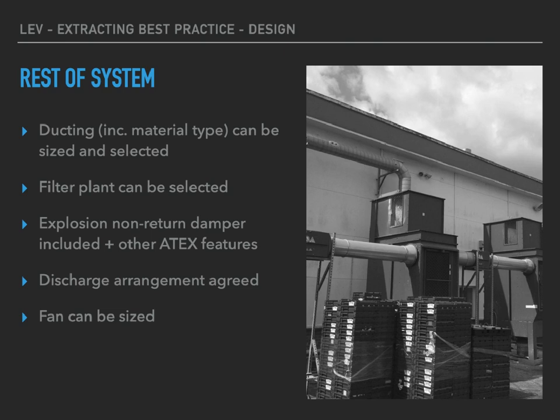We have to consider the rest of the system as well. There are many, many features that need to be considered by the designer of the LEV system. Some critical factors include the number and size of the hoods on the system, the position of the hoods, the length of the ducting runs, the fan and filter plant location, discharge arrangements, and makeup arrangements. If any of those elements change, we have to redesign the system because they are critical.